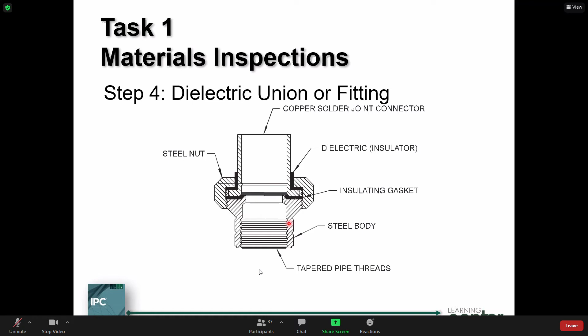Case in point, where we normally see these is on the water distribution side, like around water heaters, right? You come out of the top of the water heater with some carbon-based pipe, or a nipple, if you will, and then you transition to copper tubing. You don't want the iron-based material to come in contact with the copper tubing, because we have the proverbial anode-cathode thing here, where the corrosion is always going to be the iron-based material. That's the sacrificial lamb here, okay? It will corrode and leak.